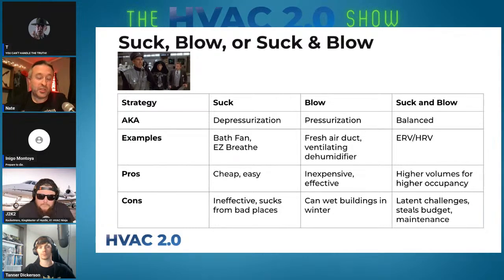They also steal budget. Pick your poison on what you're going to charge: $4,000, $10,000, and if it's a full duct system it might be $15,000 - who knows, there's a whole range of stuff here. But that's budget that can't be used for other things. I'd much rather get a high-end inverter piece of equipment with a duct going outside than single-stage equipment with an ERV. That's how we look at it.